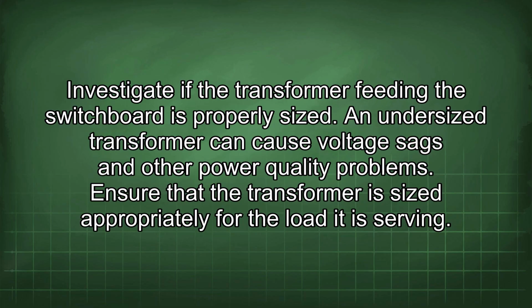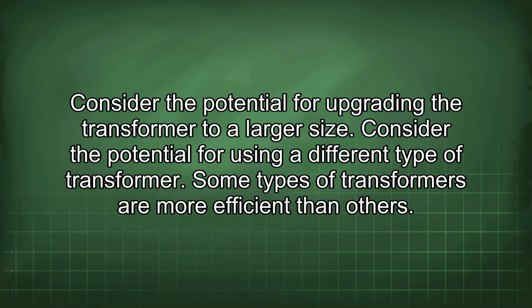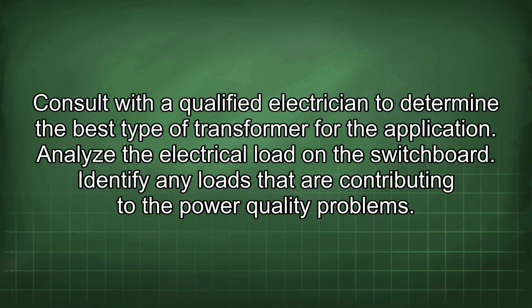Investigate if the transformer feeding the switchboard is properly sized. An undersized transformer can cause voltage sags and other power quality problems. Ensure that the transformer is sized appropriately for the load it is serving. Consider the potential for upgrading the transformer to a larger size. Consider the potential for using a different type of transformer. Some types of transformers are more efficient than others. Consult with a qualified electrician to determine the best type of transformer for the application.